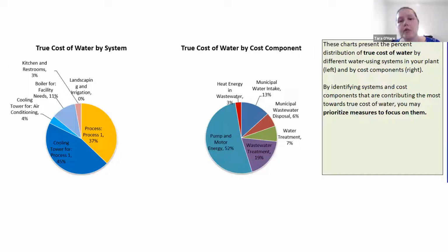The one in the middle shows the actual cost of the system in terms of energy, water, and chemicals or other outputs. In this case, cooling towers are the largest water use on the left, but they're not the main cost component in the system - they're actually a much smaller point. So you can figure out that the amount of energy used to pump and move the water throughout is actually very significant.